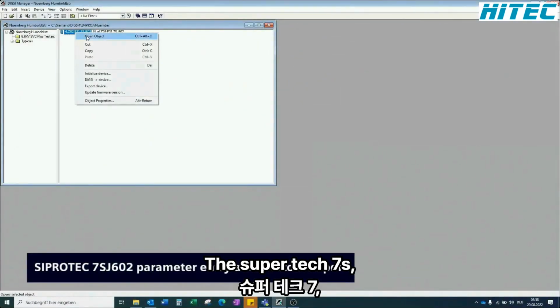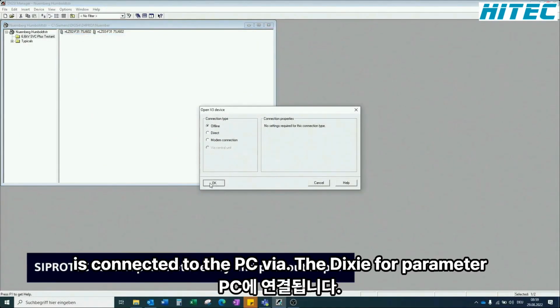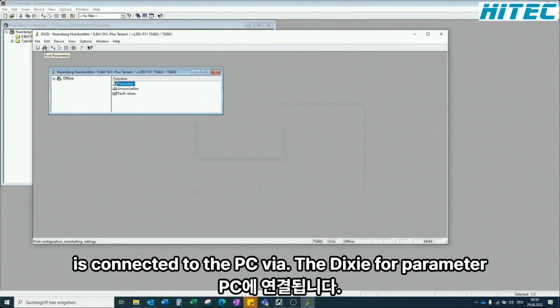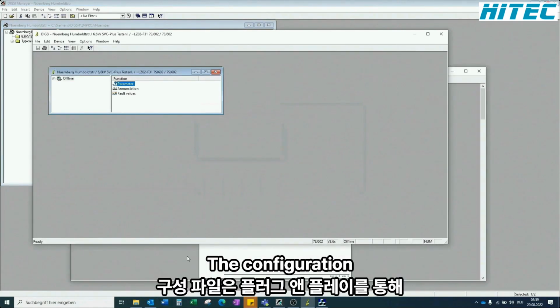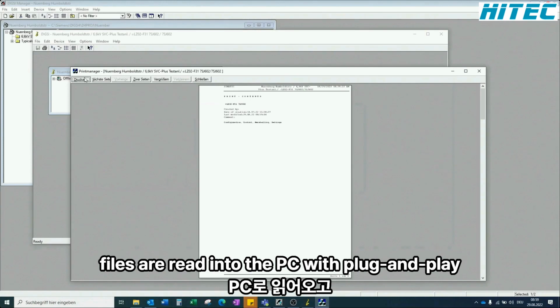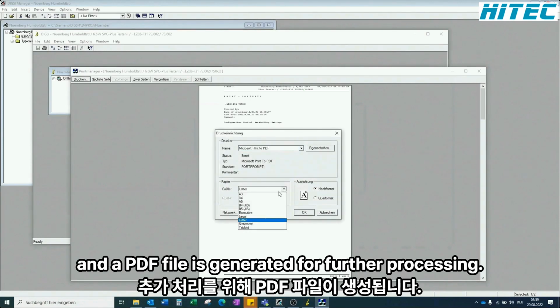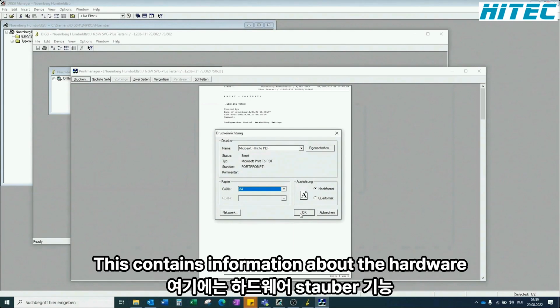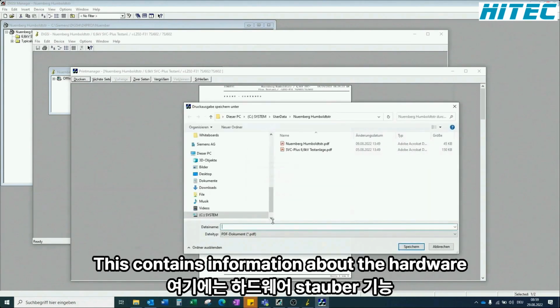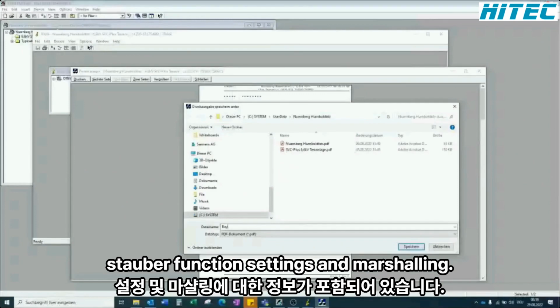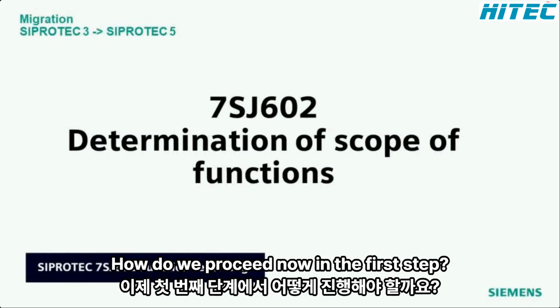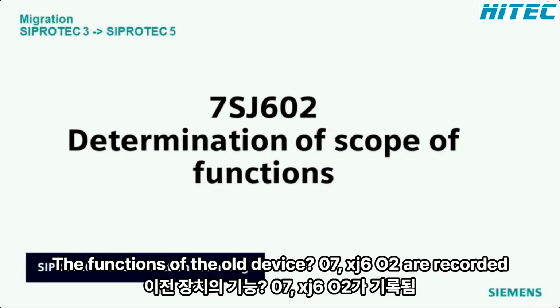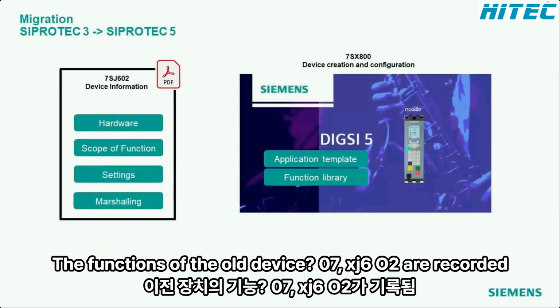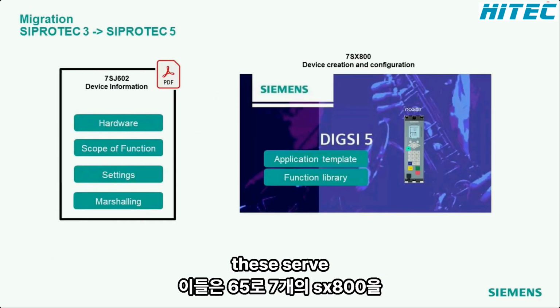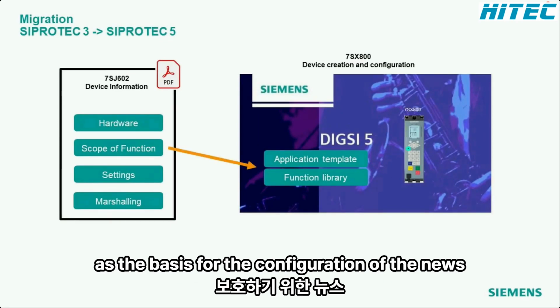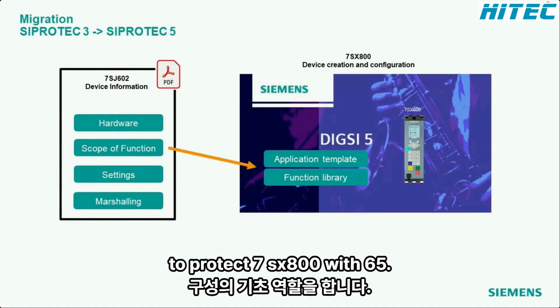The SIPROTEC 7SJ602 protection device is connected to the PC. Via the DIGSI 4 parameterization software, the configuration files are read into the PC with plug and play, and a PDF file is generated for further processing. This contains information about the hardware, scope of function, settings, and marshalling. How do we proceed now? In the first step, the functions of the old device, here a 7SJ602, are recorded. These serve as the basis for the configuration of the new SIPROTEC 7SX800.